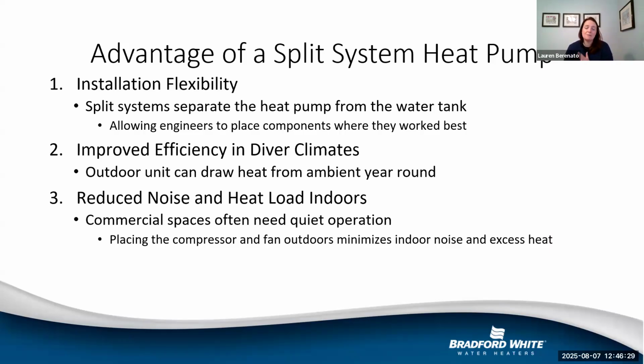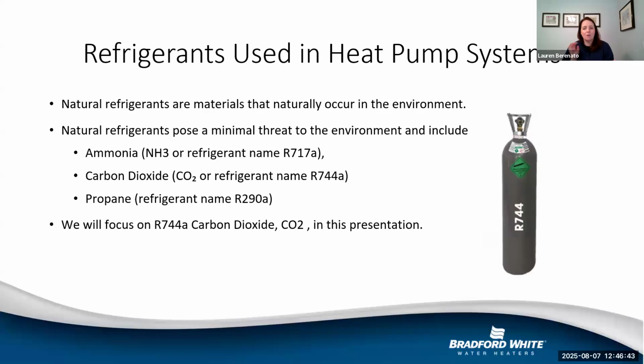Bottom line, split system heat pump water heaters are where we're giving commercial building owners as well as engineers design flexibility. I think that's what we're really looking for, more flexible solutions, and that you will find with your split system. Now, I know we mentioned a little bit about refrigerants and what is being outlawed. So R134a, very much used residentially for heat pumps. It's non-flammable. It's stable with good efficiency. Not good because it has a high global warming potential.